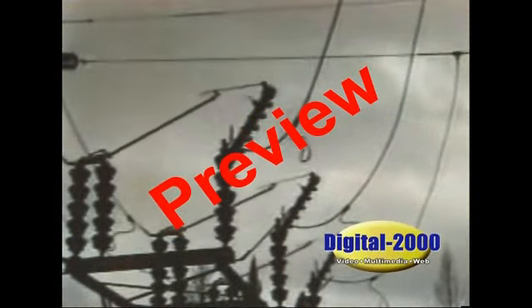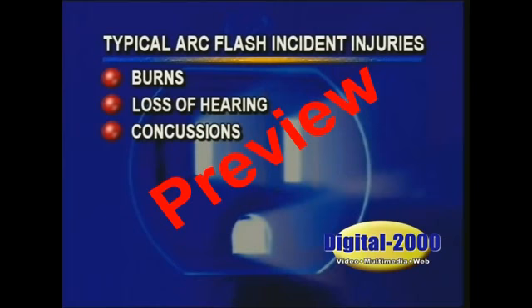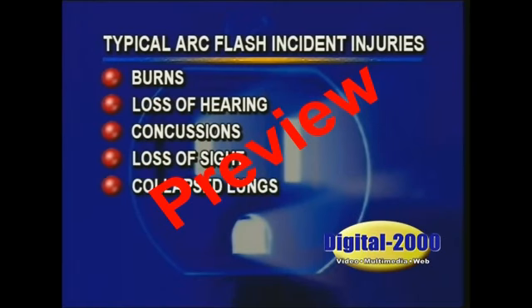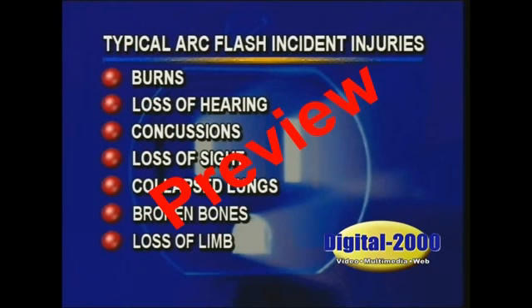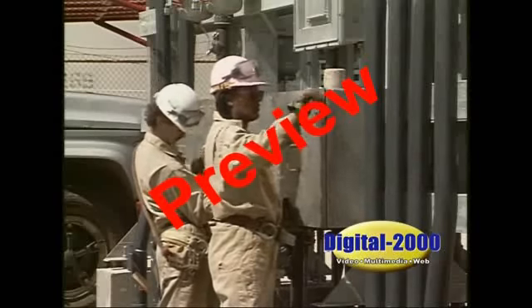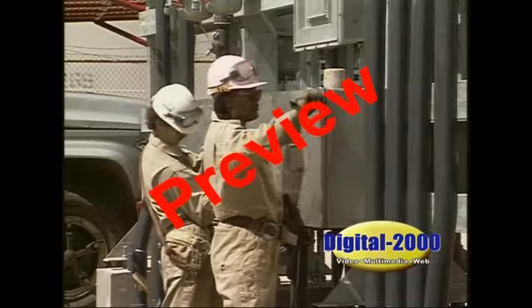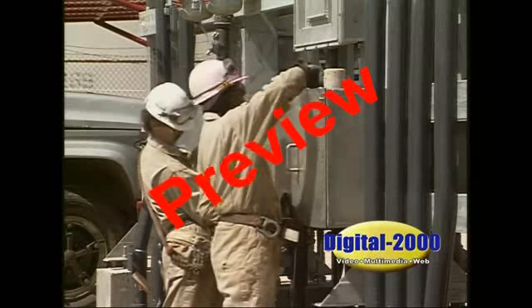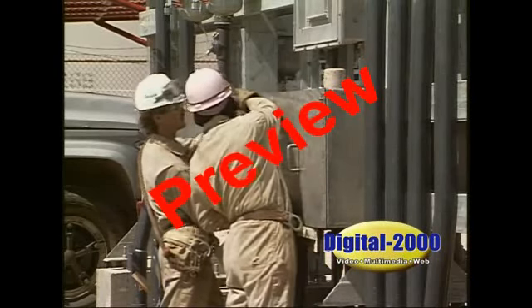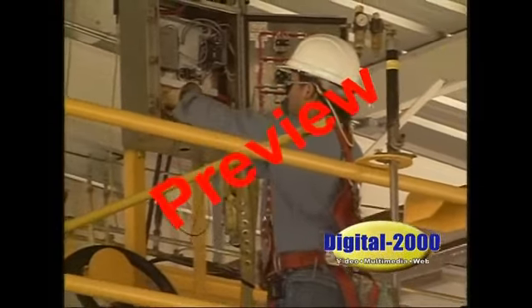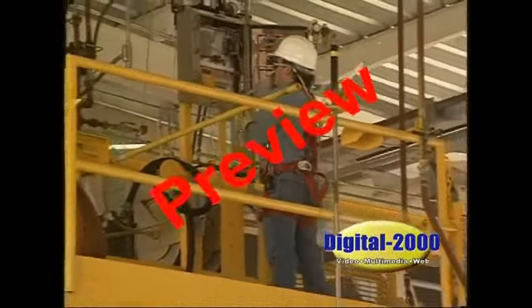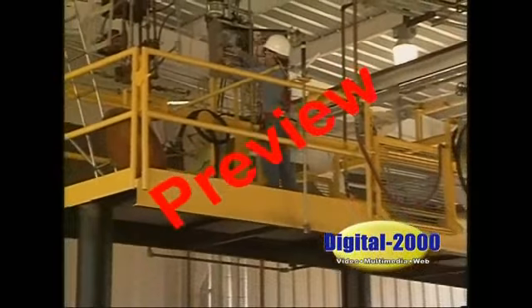Arc blasts also create extreme pressure bursts and high temperatures that cause rapid heating of surrounding air. Typical arc flash incident injuries include burns, loss of hearing, concussions, loss of sight, collapsed lungs, broken bones, loss of limb, loss of life. The best way to prevent an arc flash is to de-energize electrical circuits when equipment is being prepared for maintenance or inspection, as well as when equipment is being returned to service after maintenance has been completed. New equipment can provide for faster clearing times, alternative short-circuit detection, improved work methods, etc. that minimize arc flash hazards.